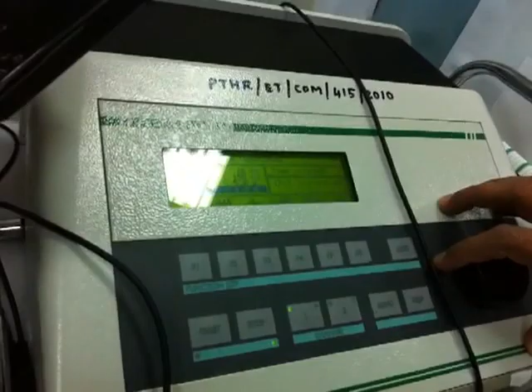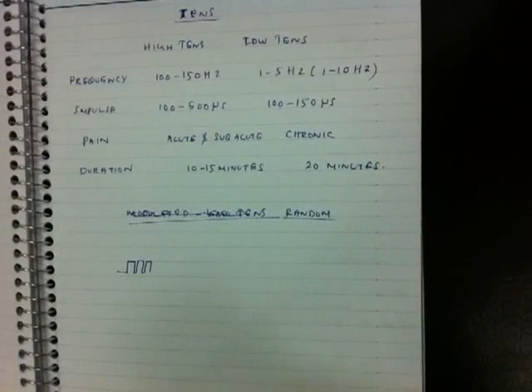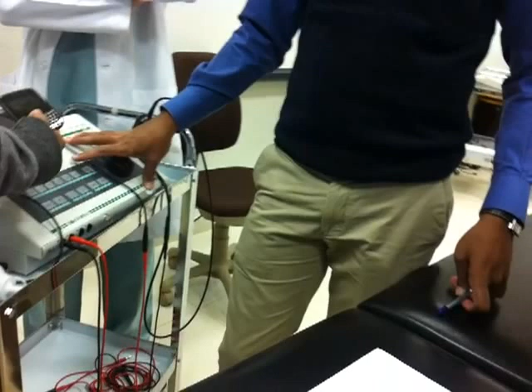Usually, we go continuous only. So if you give 5 seconds emission, you give 1 second pause, 5:1. If you get 5 seconds of current, 1 second no current, and then 5 seconds current, 1 second no current, the pause will be very short. It's like a continuous one. There is only a small gap in the waveforms, since the pause time is less. Treatment time is 15 to 20 minutes for chronic. This is for modulated. Clear with this? Okay.